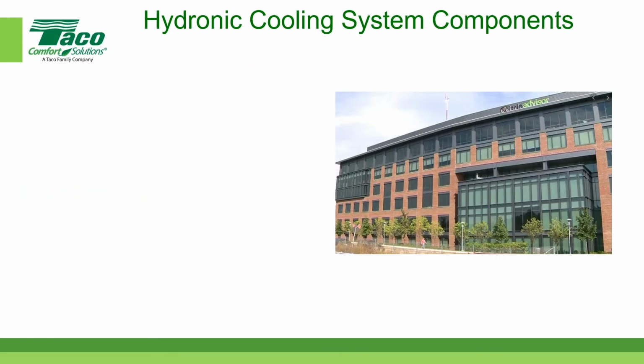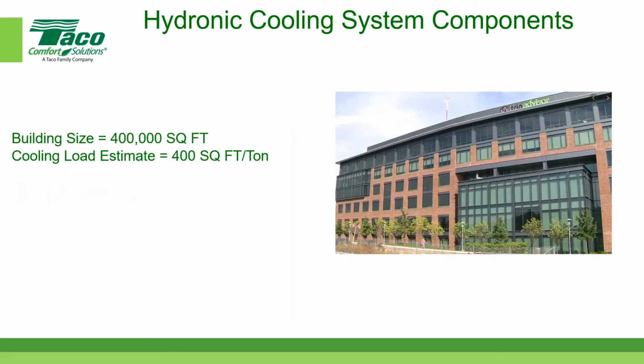And if we say that that building, 400,000 square feet, the cooling load is estimated at approximately 400 square foot per ton, which is kind of an average number that people have been kicking around for a long time. And if you take 400,000 square feet and you divide it by 400 square foot per ton, then you're going to get 1,000 tons. And if you notice, I put a little asterisk after the 1,000 tons here. I'll tell you what that means in a minute.